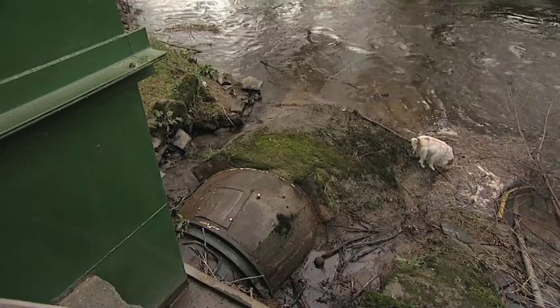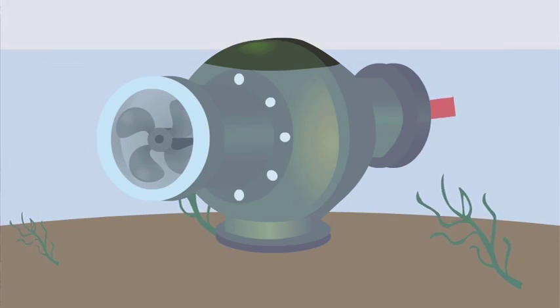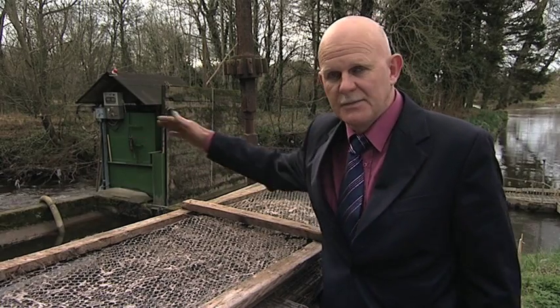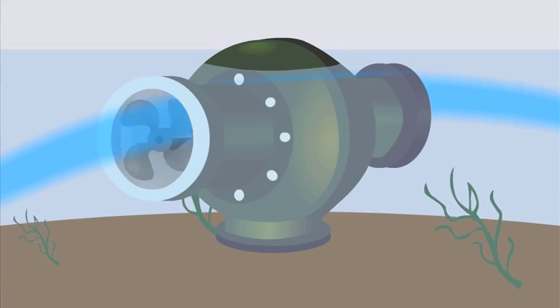This is a horizontal tube turbine. It's a lot more powerful than the other ones. This is a machine that's capable of being built from simple tools locally, anywhere in the world, even in developing countries. Water just goes straight in and straight out — there's no change in direction. It's a propeller turbine, so the propeller is on its side in a horizontal position, and it's in a little torpedo tube.